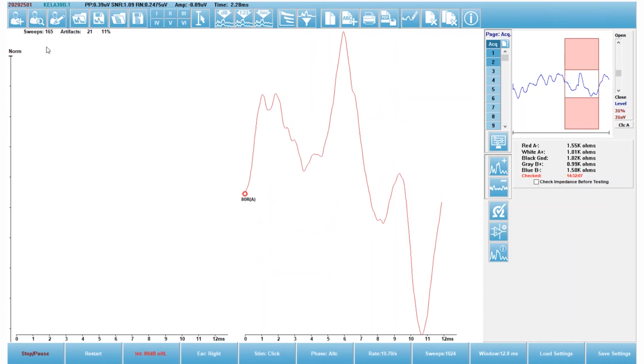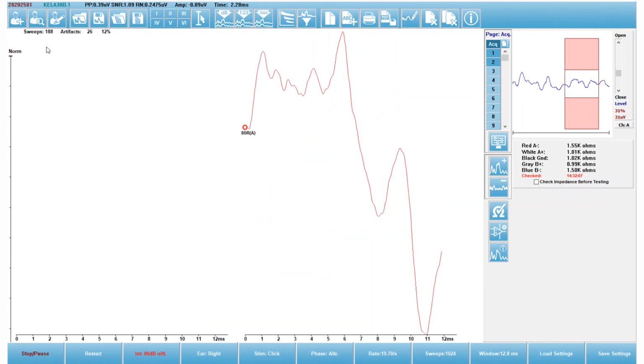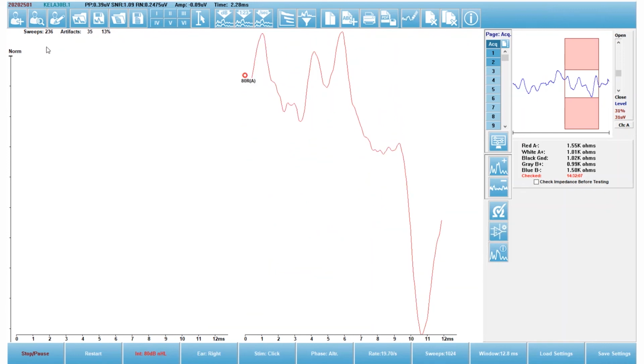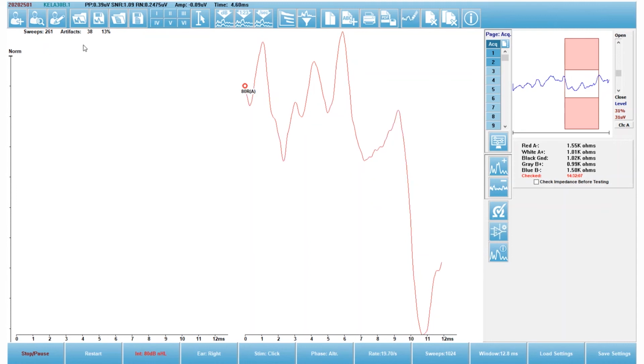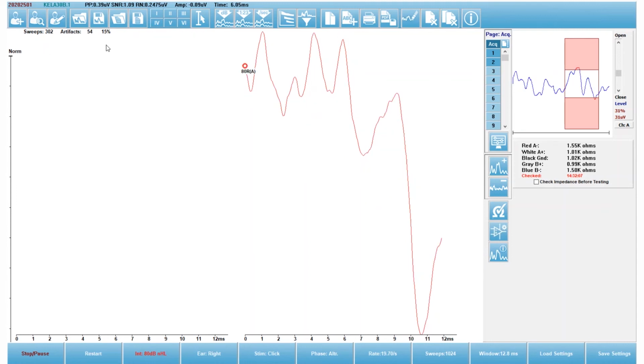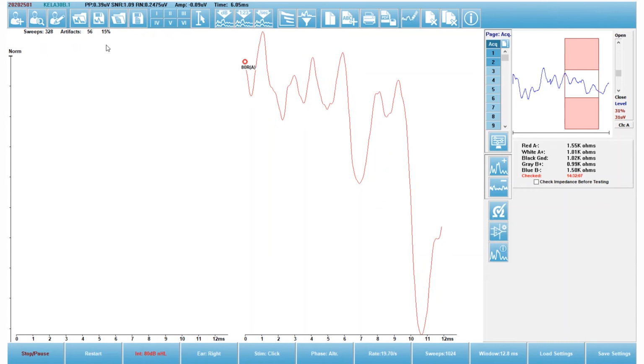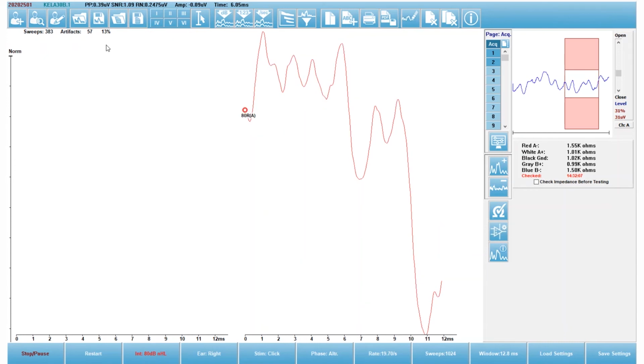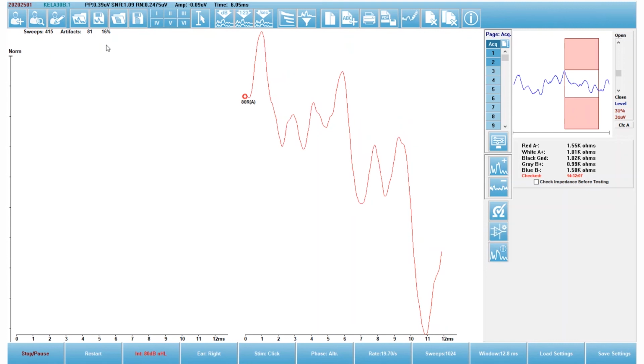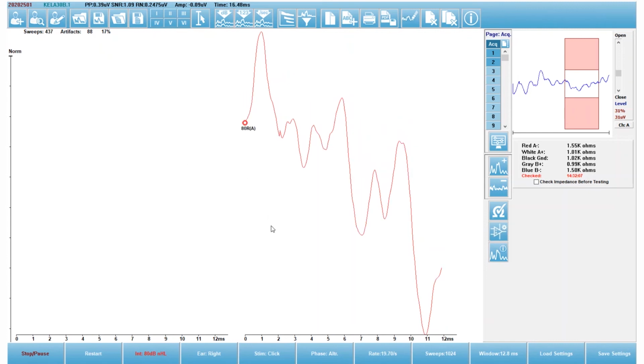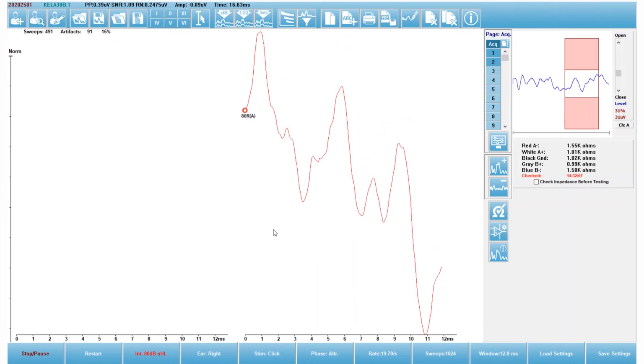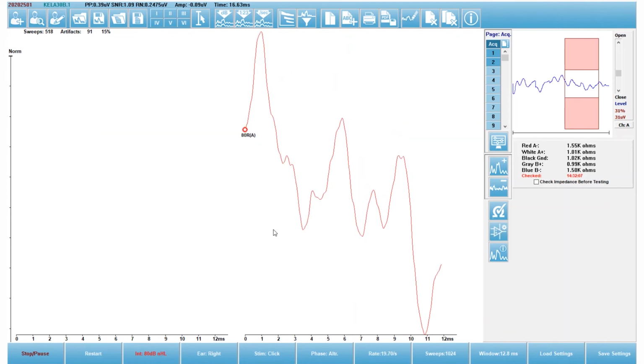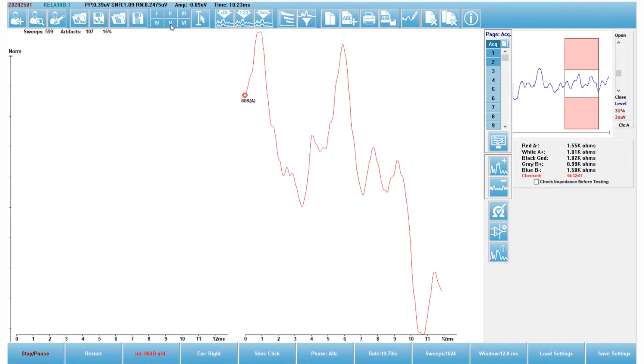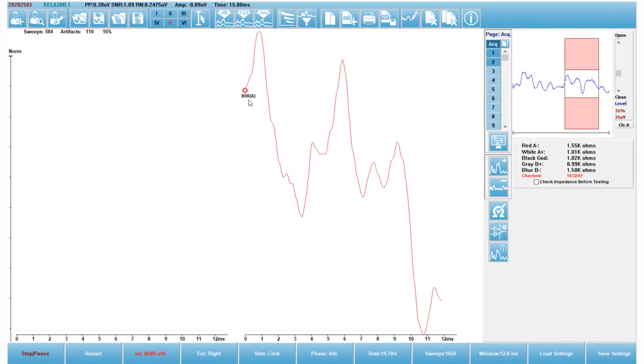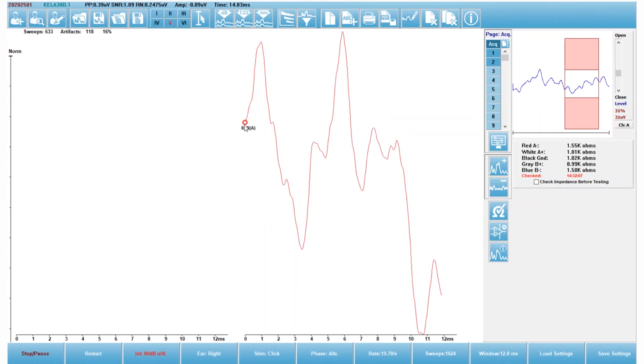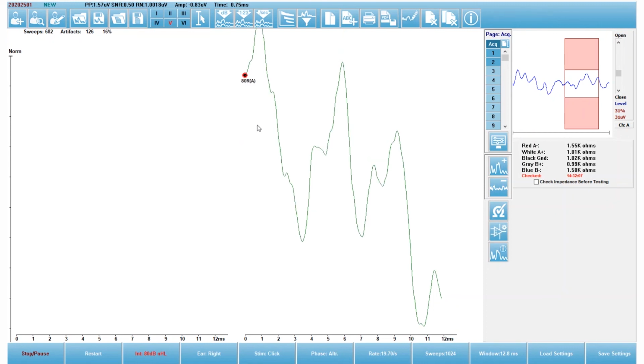If you look in the upper left corner of the acquisition screen, you'll be able to see the number of sweeps as well as the number of artifacts with the percentage of artifacts appearing. If I talk less, which is hard, the number of artifacts will drop. I can mark a waveform as I'm collecting by selecting the waveform marker, making sure I have this waveform selected. It needs to be green.